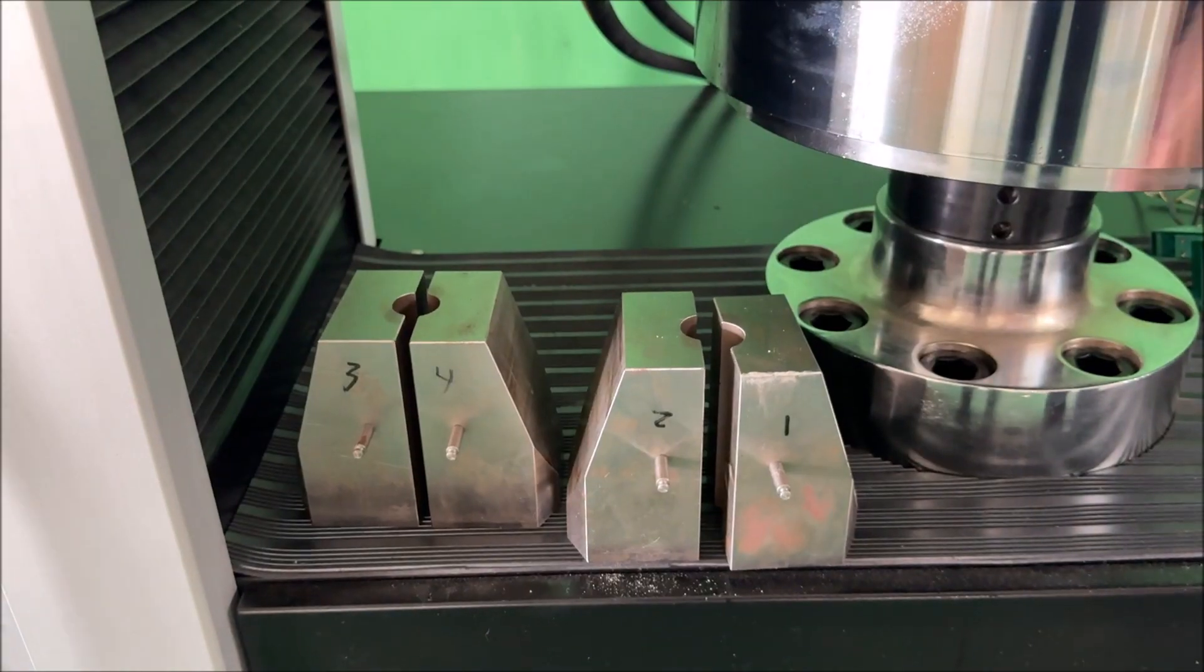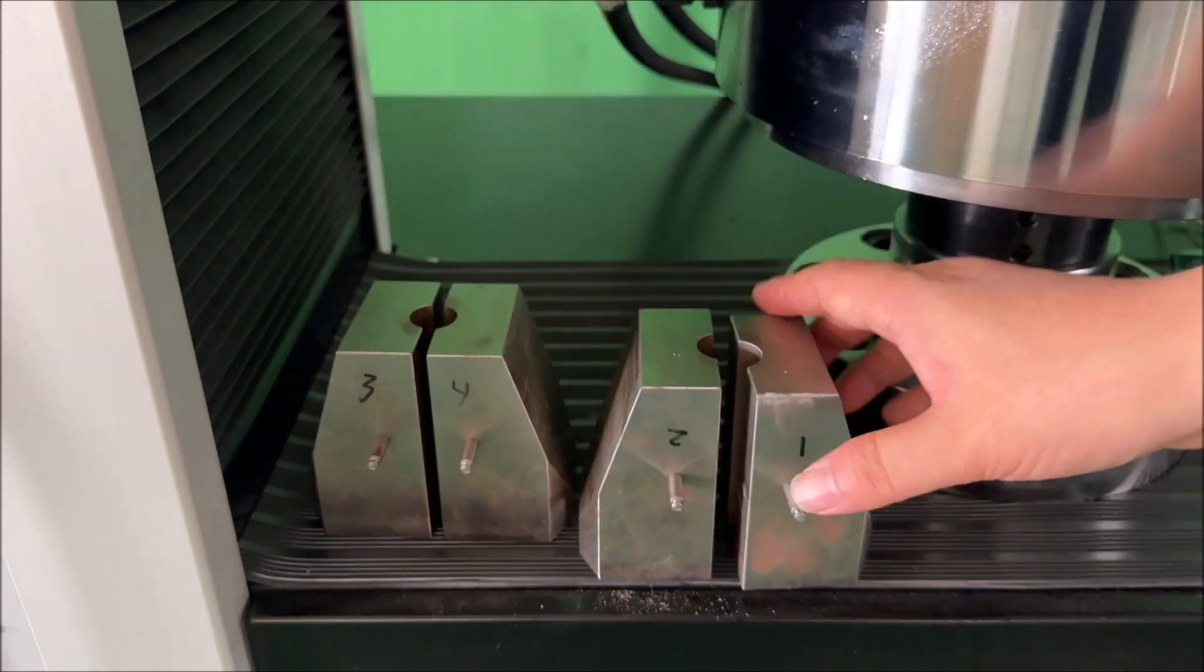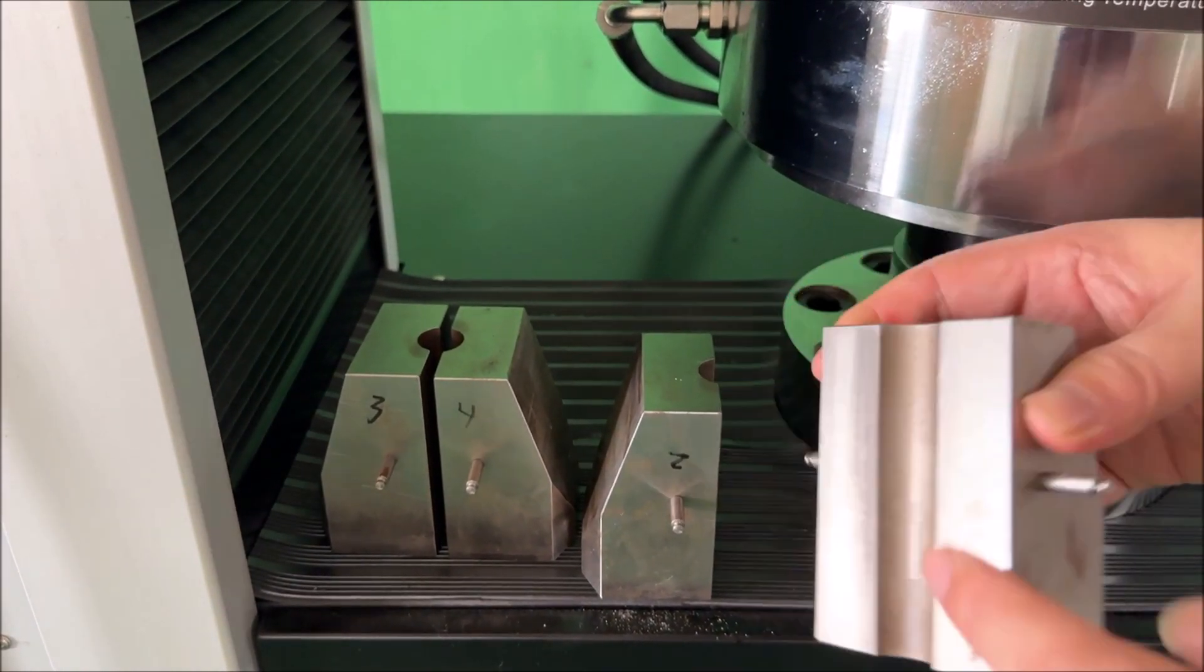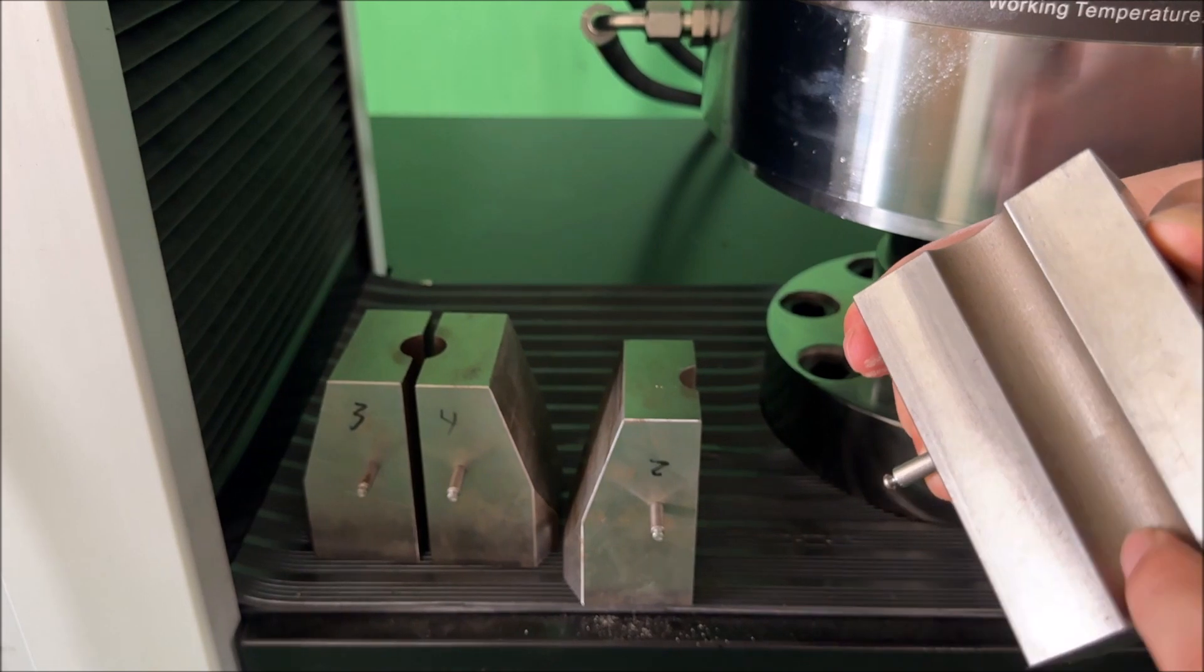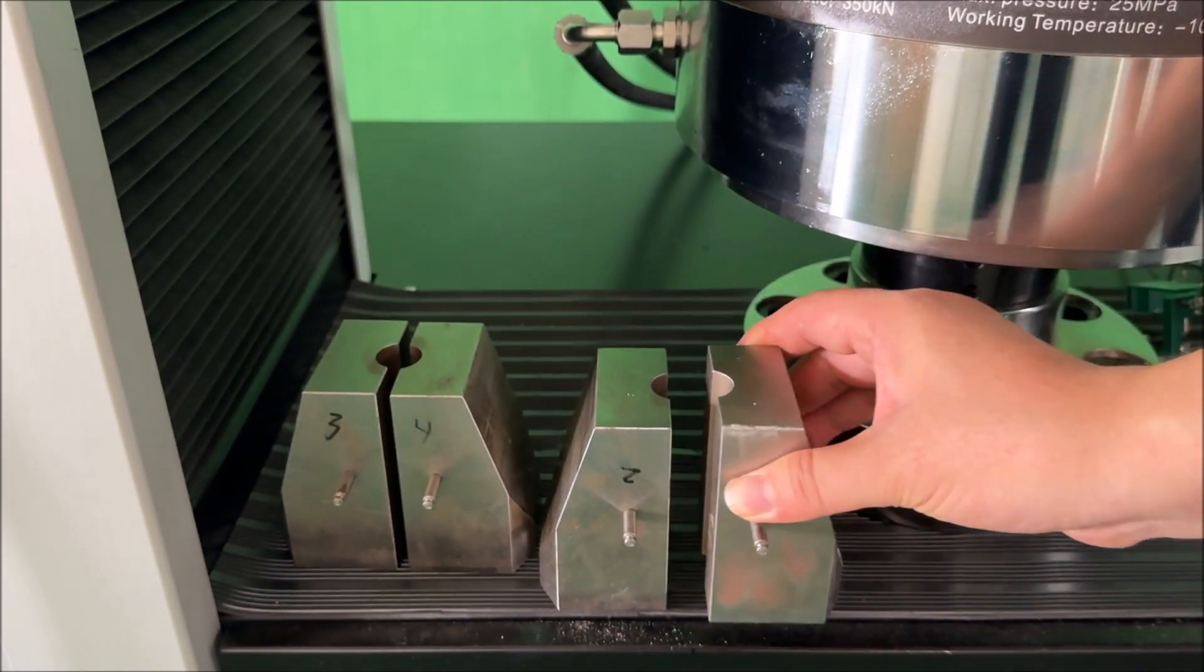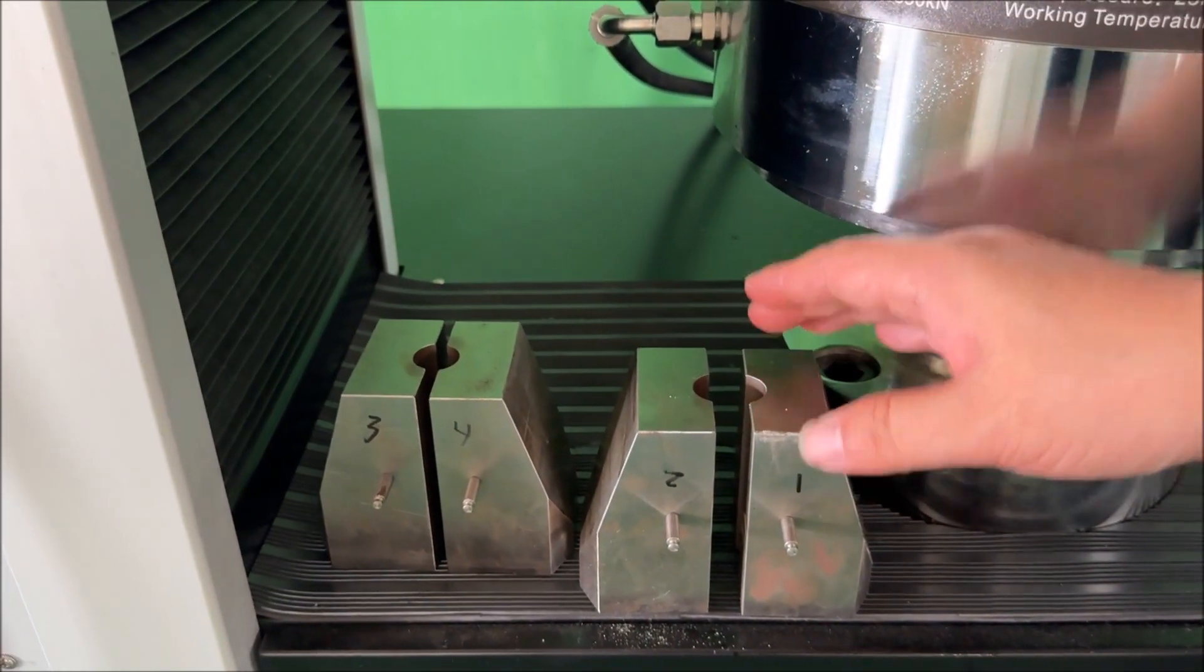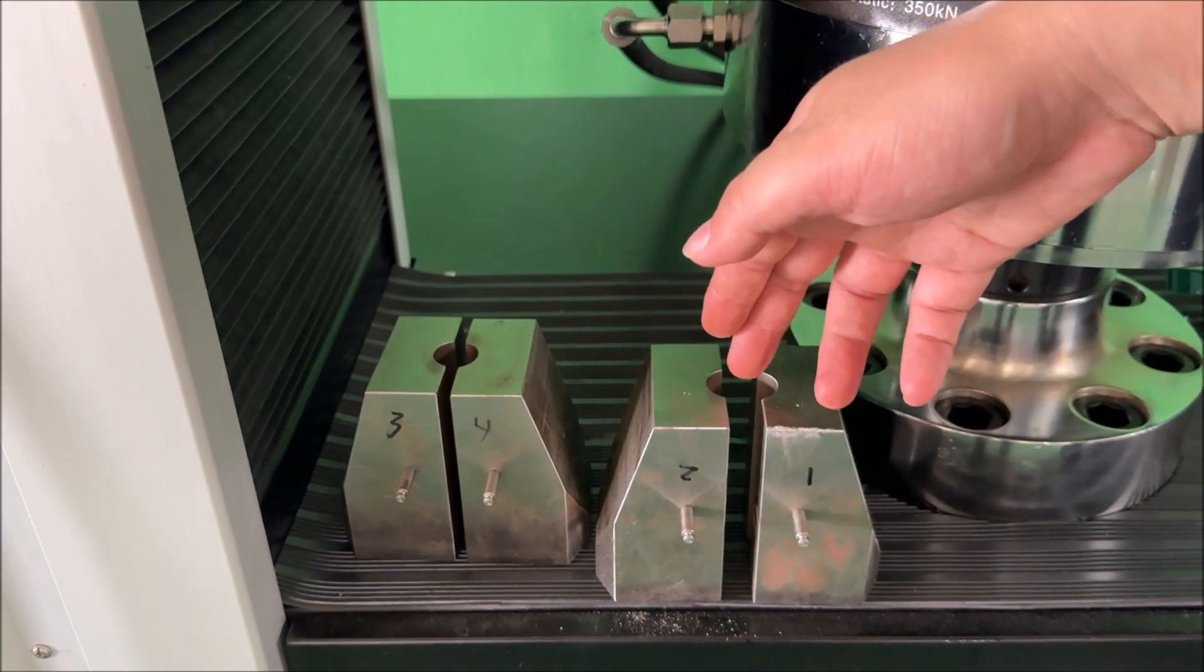These are the tensile jaws. The interior surfaces are smooth, which facilitates precise alignment adjustment. When performing your alignment certification, you can conveniently clamp your device in these jaws, which are marked from one through four.